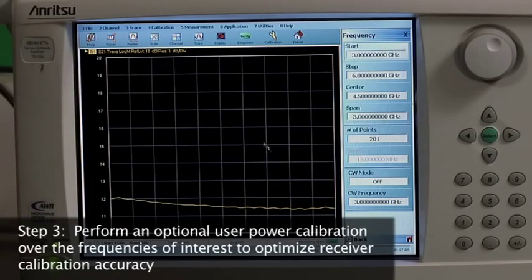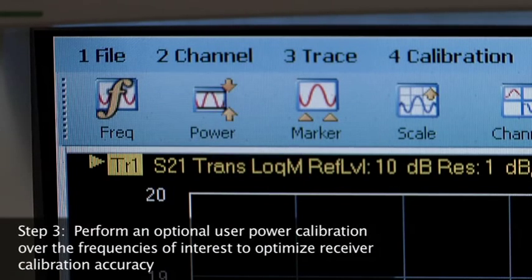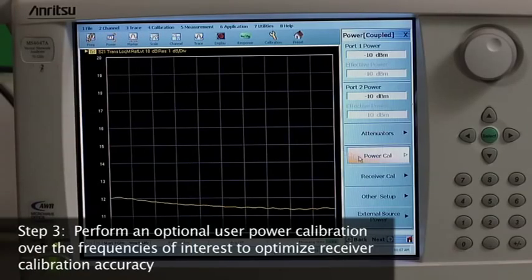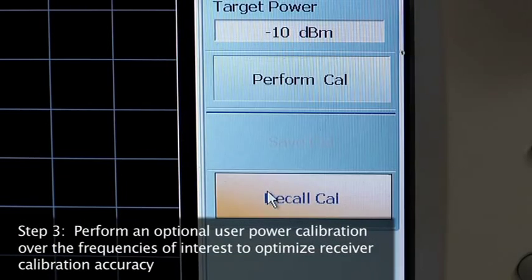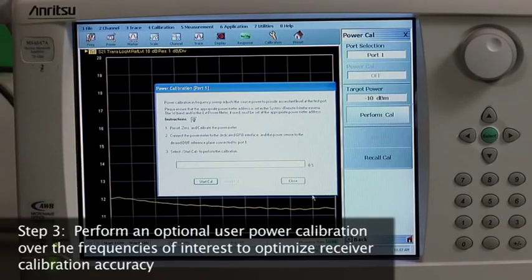Once the composite receiver has been constructed, we are ready to calibrate the receiver. To get the highest measurement quality, it's recommended to first perform a power calibration of the test port over the frequencies of interest to optimize receiver calibration accuracy. This, step three, is optional. A user power calibration is a basic VNA operation, so we will just remind you where to locate the power calibration feature.